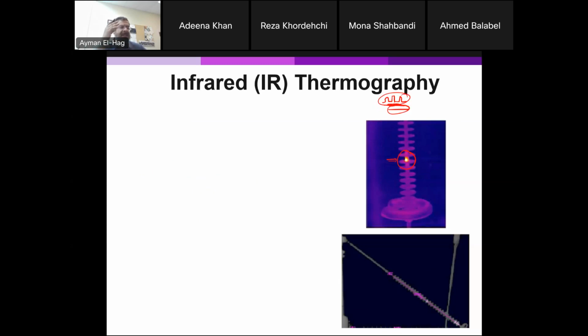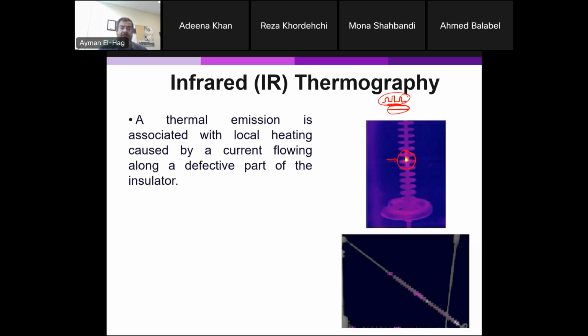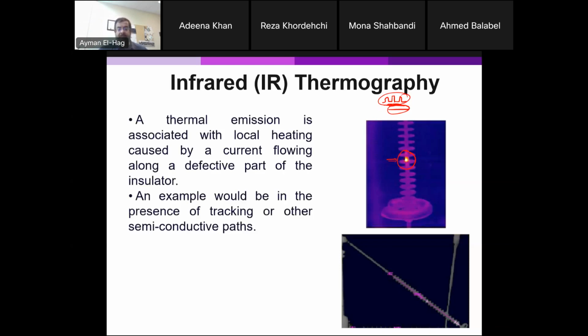And this maybe can be detected at the manufacturing premises, but as the insulator ages with time, there's an enhancement in the electric field, because there is some air void there, some partial discharge, and then some tracking starts to happen. Then you start to have an internal arcing, which will significantly increase the temperature until maybe a complete failure happens in the insulators. So the IR camera can be used here to detect internal tracking. Also, if there is external discharge, dry band arcing, it can also be detected using the IR camera.